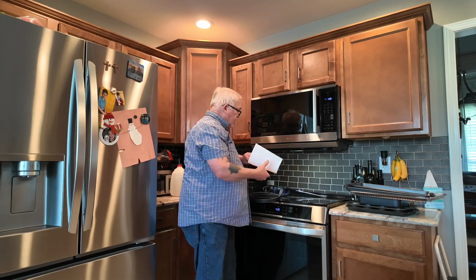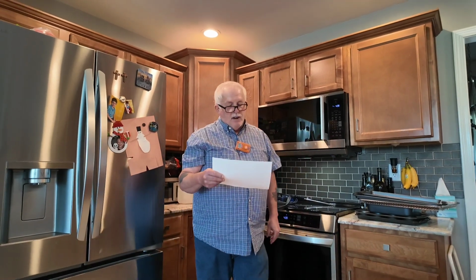And then finally, it says, can I identify the action levels for the CO test results in the oven in accordance with ANSI BPI 1200. Well, ANSI BPI 1200 says oven or broiler, 225 parts per million as measured. Again, everything you need is right here.